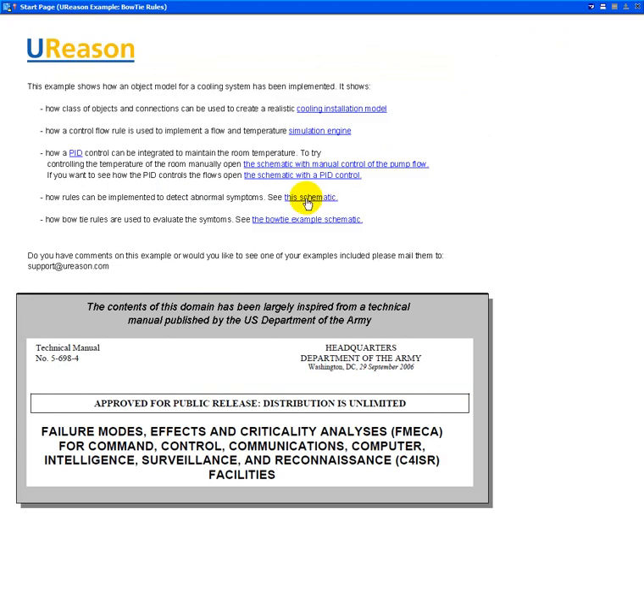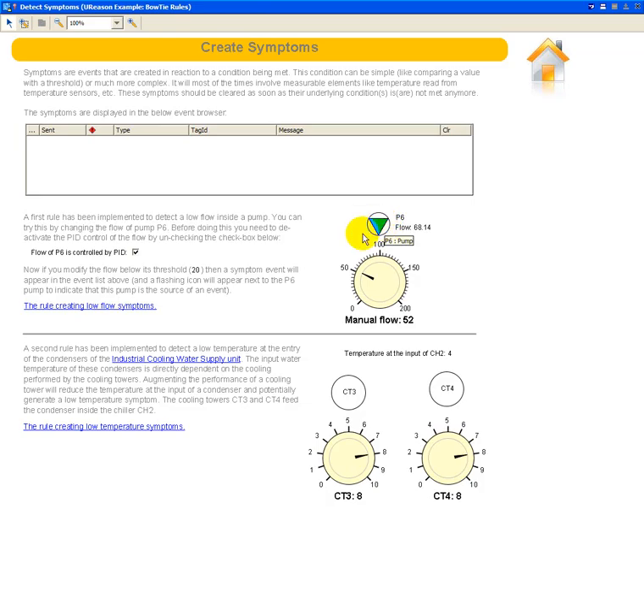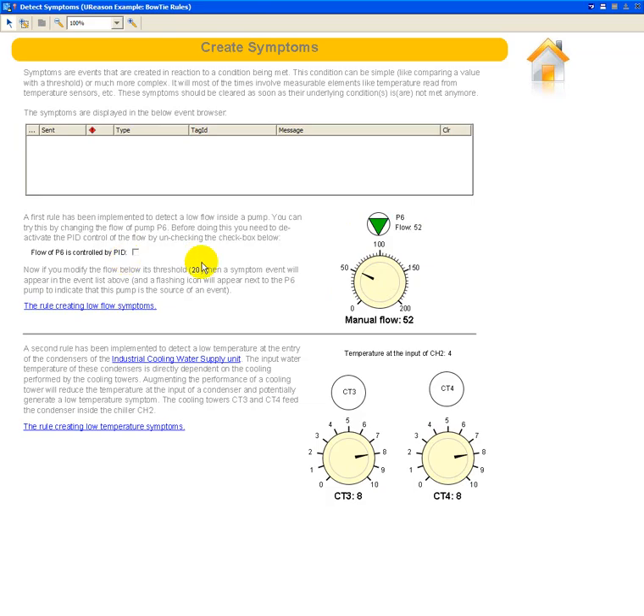The fourth part of this demonstration is showing how rules can be implemented to detect abnormal symptoms. And this is done on this page here where again we are playing with the P6 pump. I'll also take control manually of the flow of that pump. It's actually now around 50. But if for any reason I decrease that flow below a certain threshold that is set to 20, then a rule will react.